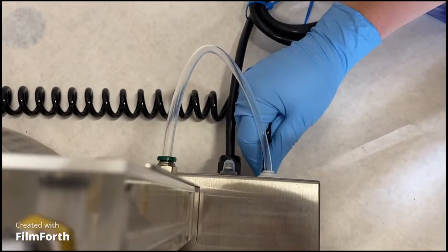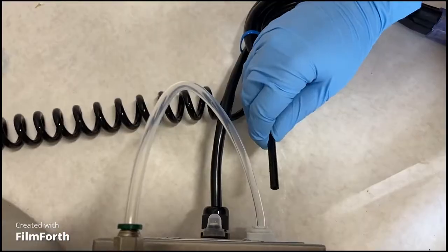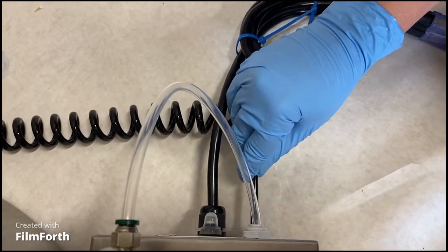Then, check that the gas flow is reaching the bath case. Disconnect the gas tube from the back of the unit, turn on the gas source, and confirm that there is flow.